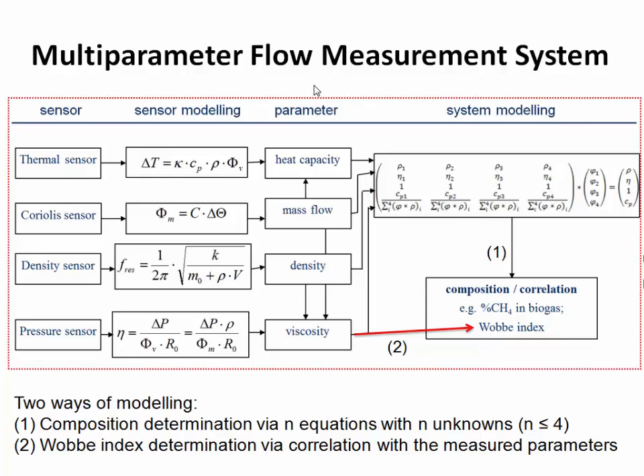So in this current system, we are limited to gas mixtures consisting of 4 different gases. So here you see a matrix, and with this matrix we are able to find the composition via n equations with n unknowns. So this time it's 4. So then we get, for instance, the percentage of methane in biogas. And the other way is how we determine the Wobbe index. It's, for instance, via correlation with the viscosity of the gas mixture. So we can determine that via correlation, this way, the second method.